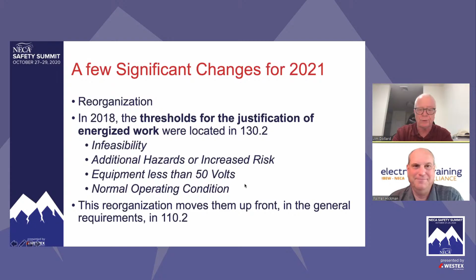Equipment less than 50 volts, well, we're going to have to take a look at the capacity. You have to consider the capacity, because the standard doesn't apply, for example, at 48 volts. But if we had a 12 volt car battery, everybody that's listening has made a mistake with a 12 volt car battery, and you didn't set your clothes on fire and you didn't get third degree burns. You were just more careful and you went right back at it. But if we took 4 of those and put them in series, we got 48 volts. And if we take 100 sets of those, we put them in parallel, we still have 48 volts, but nobody will put a wrench across that, because we understand capacity. And that's what that justification threshold is talking about.